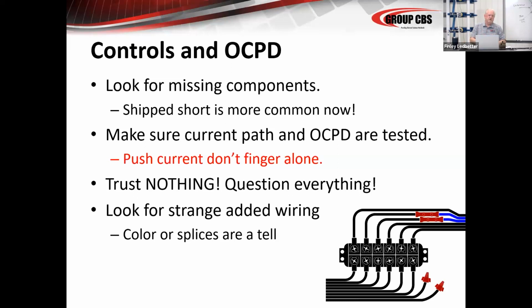You see stuff that doesn't look right, then you have to dig deeper and dig deeper. You see all this nice gray wire that's all looped in properly. Then you see two yellow wires that are tied into these looms with wire ties going over and clipping into a jumper somewhere. That is a red flag. You need to go back and figure out why that is there, determine if that jumper needs to be there, if those splices need to be there, and was that added way late, way early.